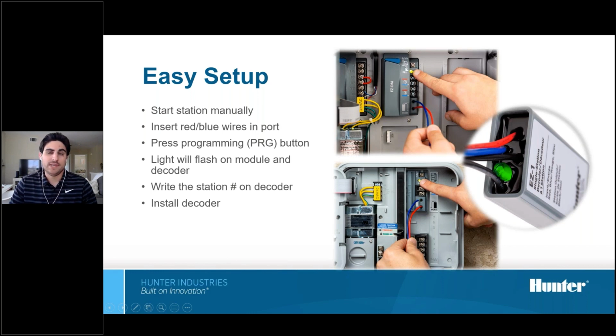If you wanted to do a PMV output, all you have to do is plug those red and blue leads into the decoder port, hit that PRG button when no stations are running, and boom, you've got a pump master valve output ready to go on your 2-wire path. Be cognizant moving forward, though. Some guys have accidentally programmed a decoder without running a station and ended up with multiple PMVs they didn't want. Make sure you actually start that individual station and write down on the decoder what station it should be, and for PMVs, don't start any stations, but keep those separate from the rest of your decoders.